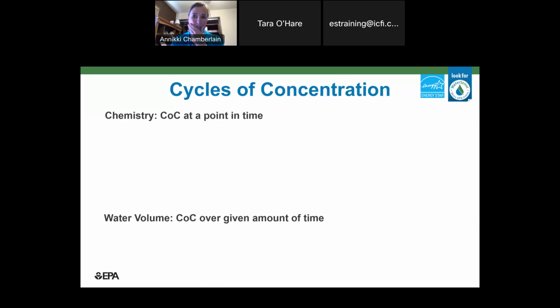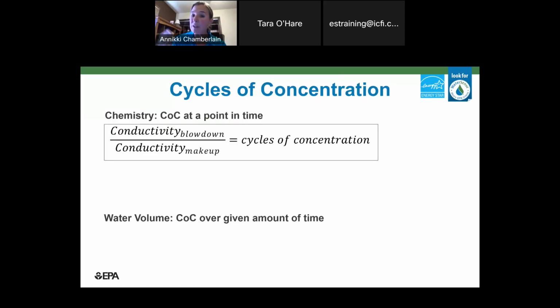Again, we're not going to dive too deep into it because I want to get to some case studies, but basically that's the main efficiency metric. And as we'll see through this, it's a great operating metric from day to day to see how your tower is doing. Typically you measure the cycles of concentration with chemistry. We look at the chemistry of the water going out, divided by the chemistry of the water coming in, and that gives us our cycles of concentration, basically showing us how many times we've cycled those minerals up.